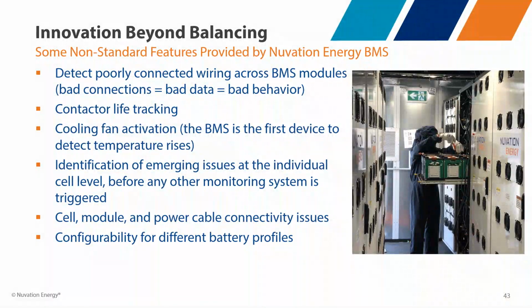Before it agrees to close a contactor and put a stack online, the BMS first needs to make sure it can functionally and safely open that contactor and take the system offline if there's an issue. This is part of UL 1973 certification, doing contactor life tracking.